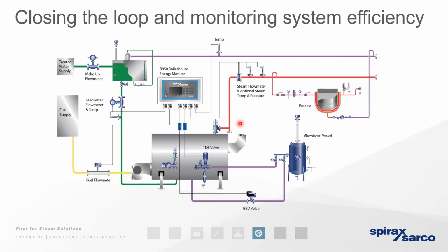So let's say, for example, over a period of time, we found that the steam flow rate had remained consistent, as had the amount of water being consumed from the feed tank. But the amount of water that we were taking from the mains had shot up. And imagine we identified we were using more and more fuel. Well, the console would tell us in real time. It could send an alarm, send a reading to quantify these costs in financial terms. And we may then decide to walk the plant and identify what's gone wrong with the distribution network.